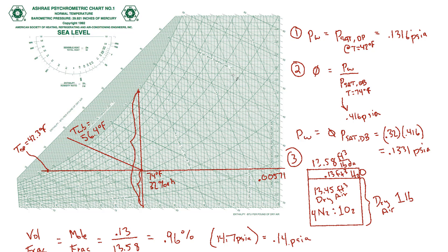is that water vapor contributes relatively little to the total pressure of air, even moist air. So maybe up to about 5%, let's say, you know, in this case, it was around 1%, but it's fairly dry. So you could imagine a case where the moisture content is considerably higher, and that percent would increase, but not by a whole heck of a lot, maybe up to about 5%. And then when the temperatures get very high, higher than what's offered up on the psychrometric chart, then maybe it could be higher still. But you should expect the partial pressure of water vapor in air to be well under 10% of the total pressure for most HVAC applications.